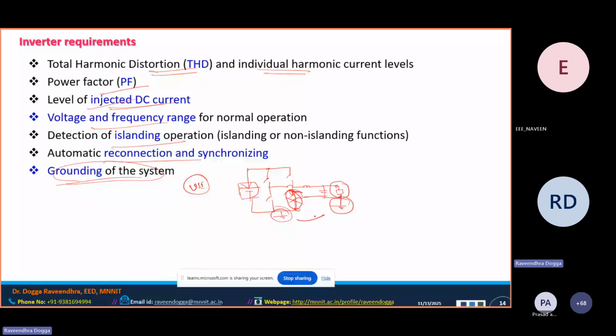In case of solar, if you see in terms of safety standards, most of them have a restriction that your PV module voltage should not be more than 100 volts. That is one requirement. Also, if it is more than 50 or 60 volts, some countries require that your PV negative terminal should be grounded, and also your load side neutral should be grounded. These kinds of standards exist to ensure very good safety.